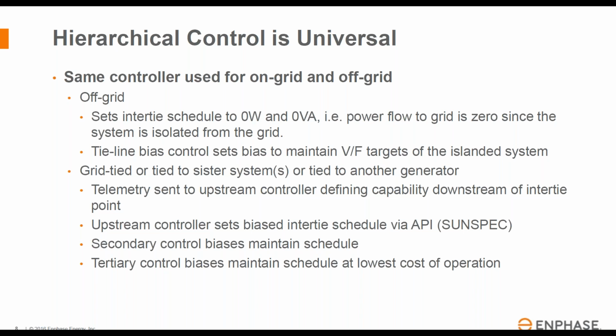And then simultaneously, we would set the intertie schedule to produce basically zero power and zero reactive power at that intertie. So it tells the system that there can't be any power flow to the grid since the system is essentially disconnected from the grid. And then we have a tie line bias control signal that sets a bias to make sure that the system is maintaining the voltage and frequency targets of the intentionally islanded system.